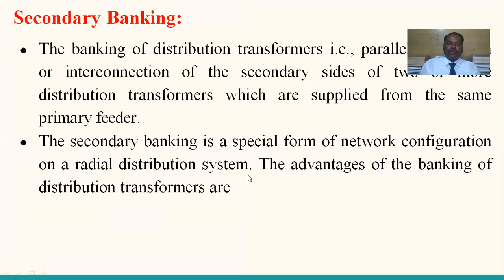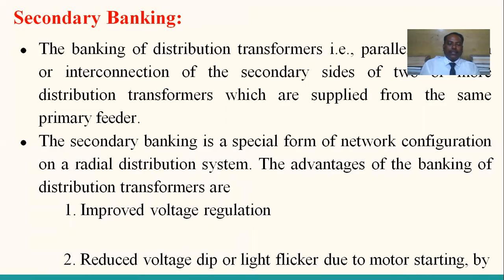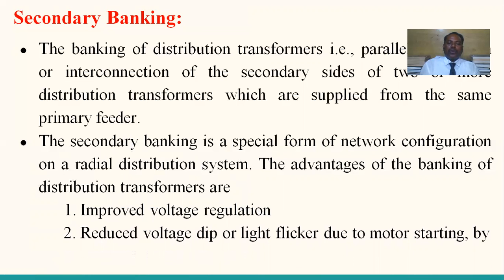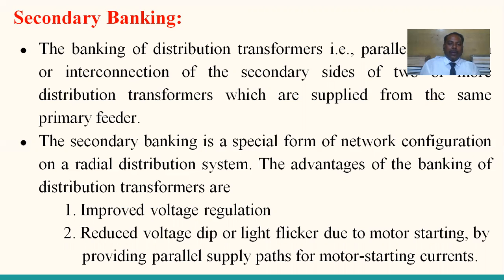The advantages of the banking of distribution transformers are improved voltage regulation. Improved voltage regulation is the most important for us. Voltage regulation is good in the sense that voltage drops are low. And the second one, reduced voltage dip or light flicker due to motor starting, by providing parallel supply paths for motor starting currents. So see here.